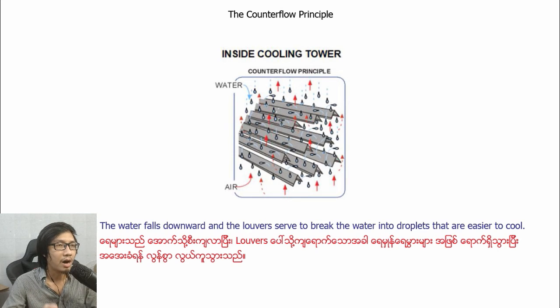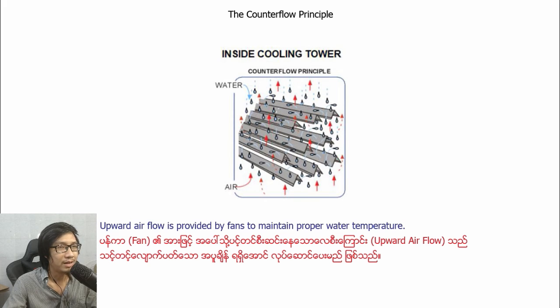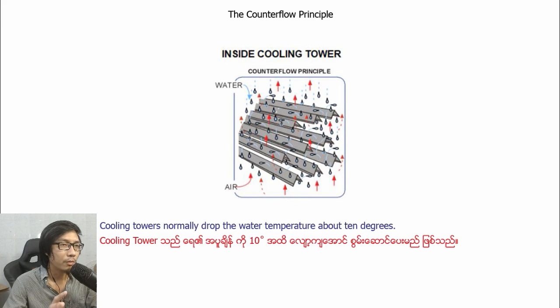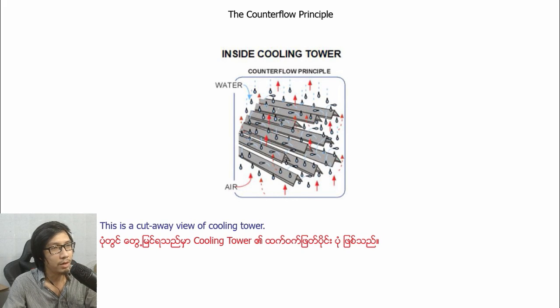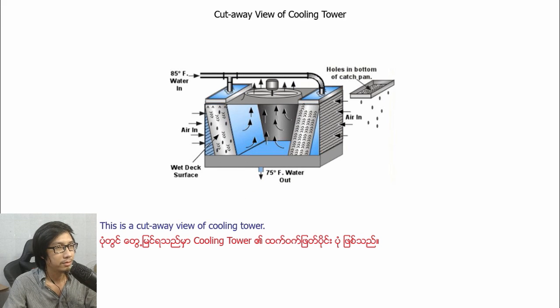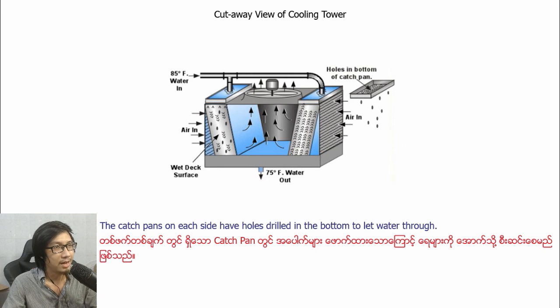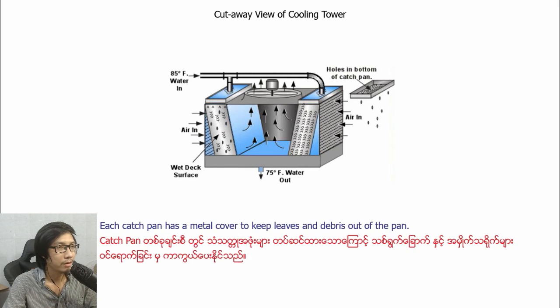The water falls downward and the louver serves to break the water into droplets that are easy to cool. Airflow is provided by a fan to maintain proper water temperature. Cooling towers normally drop the water temperature about 10 degrees. This is a cutaway view of a cooling tower. The catch pan on each side has holes drilled in the bottom to let water through. Each catch pan has a metal cover to keep leaves and debris out of the pan.